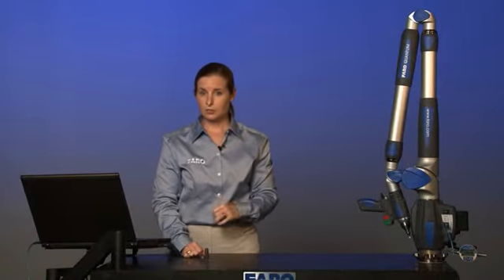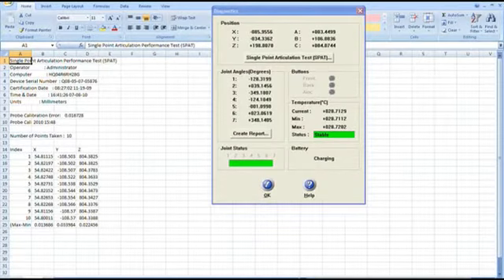Pressing the red button prompts you to save a CSV file. This file will have the data that you just collected, and tell you whether or not your arm is measuring within the accuracy. Select Save. Review the results, and if necessary, send these in to FARO Customer Service, and they can help you review these and see whether or not the SPAT test is within your limits for your specified equipment. What you've just seen is a check of the mounting stability of the FARO arm and the SPAT test, or the single point articulation test, to verify the accuracy of the FARO arm.